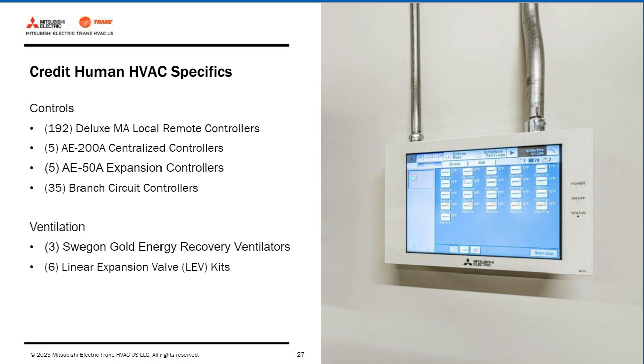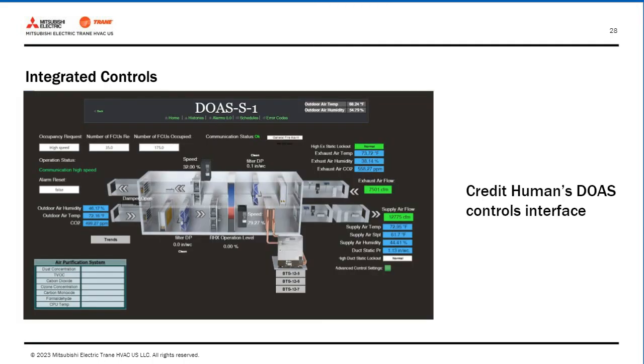So they use the same condensing unit to serve the refrigerant coils in these dedicated outside air units on the roof. Next, we're going to talk a little more about how this control system integrates with the rest of the building systems. The Credit Human building is incredibly well integrated. It's actually one of the most tightly controlled buildings in Texas. This is thanks to the robust control system we talked about on the previous slide, and how it integrates with the building's other systems, including the ventilation, lighting, security, and a host of other items.